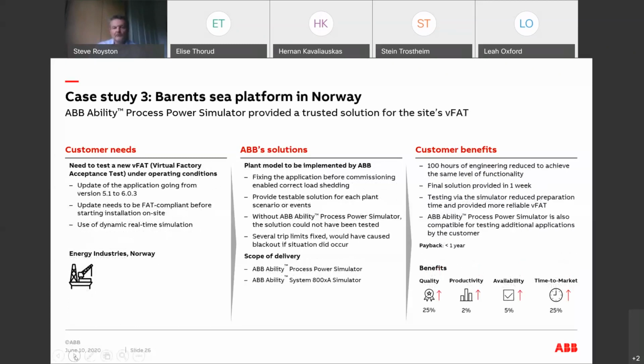So this is another example of an upgrade where the customer required us to do a new FAT after the upgrade to make sure that the application is working as it was before the upgrade. And it is actually simpler and quicker to set up a simulator of this type and build a model, and you don't need to have everything included. However, medium voltage is typically something that should be included, and also your sheddable loads. Where are they? Are they in low voltage or medium voltage? So you don't need to represent everything, but it's so simple and very quick to build the model, and it's actually quicker than setting up a test system with IO testing and feedback logic for this case, and you get so much more out of it.